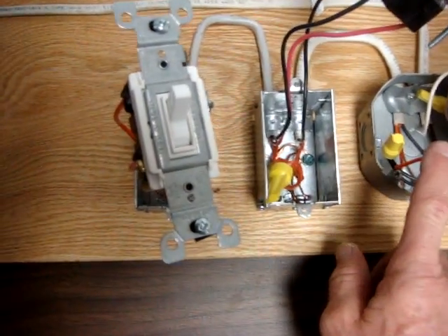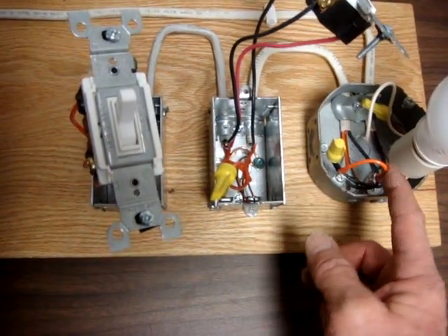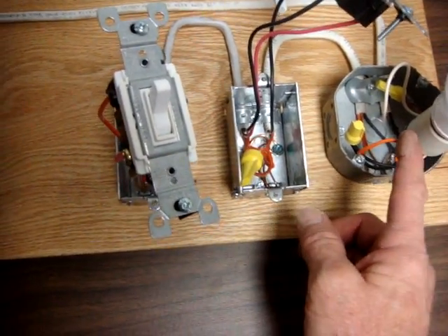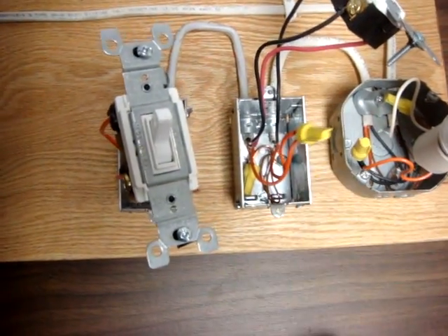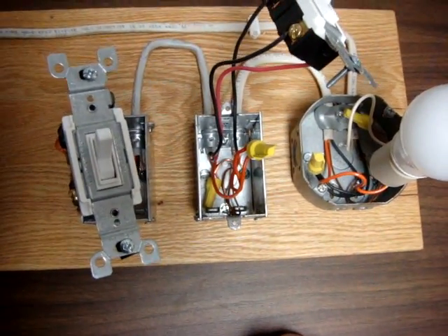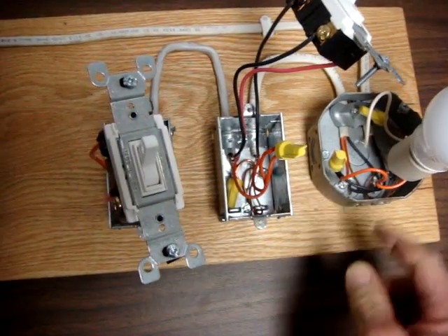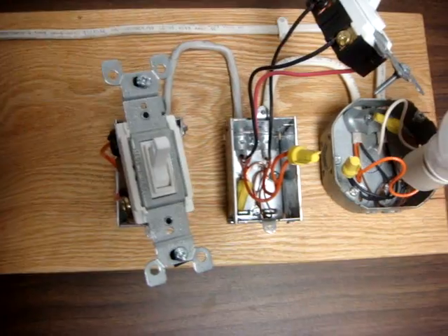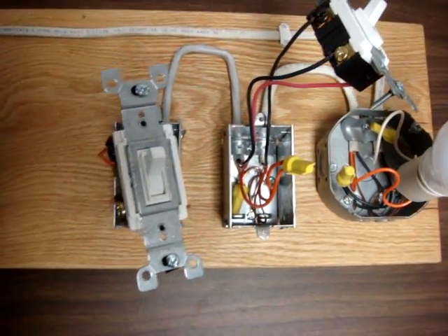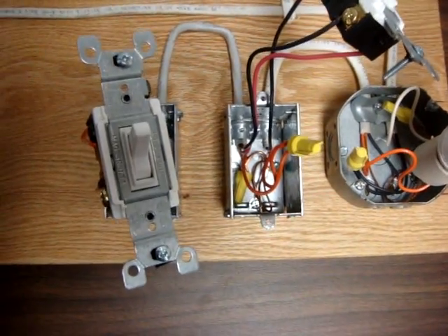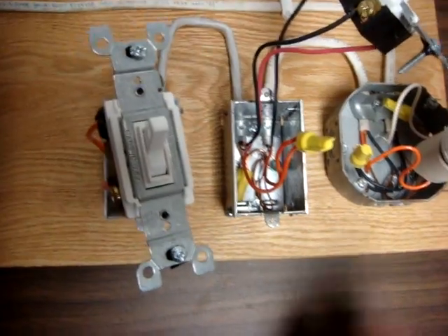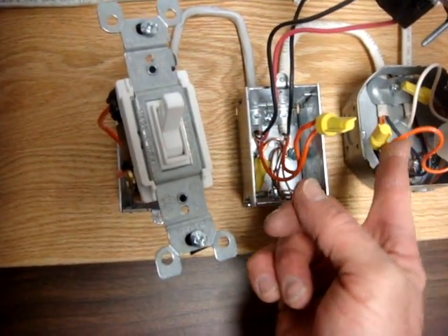You can use any color, as long as it's not green, white, or gray. Green is reserved for grounding, white and gray are neutral colors. But you could use pink, turquoise, red, purple, brown, orange, yellow, anything that you like that would be a current carrying conductor color.